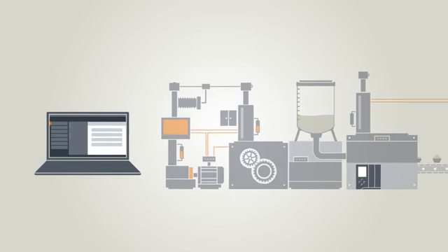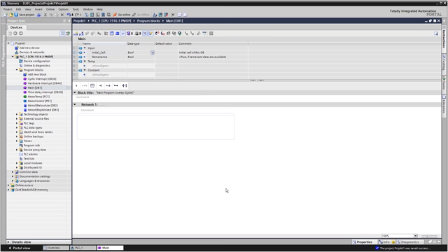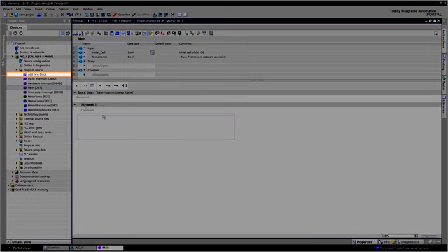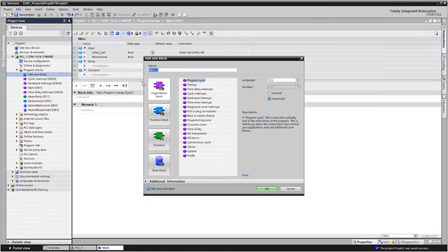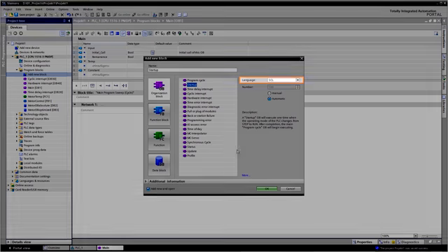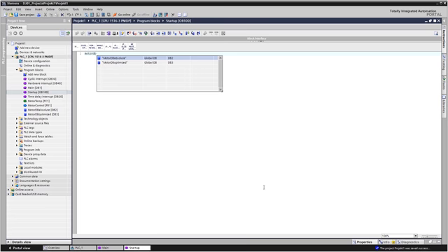How does that look in the TIA portal? The TIA portal offers assistance in the creation of new organization blocks. Various OB types for events are available under Add New Block. Cyclic OBs, Startup OBs, Alarm OBs, Fault OBs and MC OBs for the operation of drives. The program editor in the specified programming language opens automatically when you are creating a startup OB. You can now define the system behavior for startup or restart, let's say before cyclic operation commences.